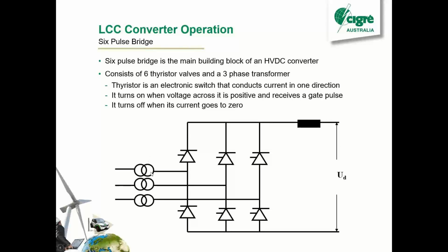In the context of HVDC, these thyristor valves don't have to be a single thyristor, right? These can be made up of multiple thyristors in series. On one of our poles, we've got 66 in series to make up one of these valves. But just to show, we're representing it as one device here.